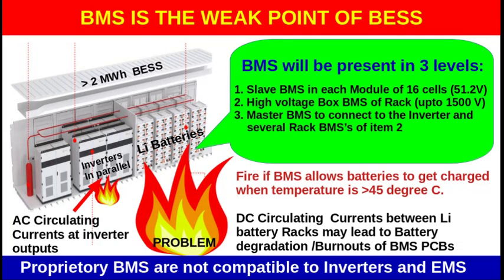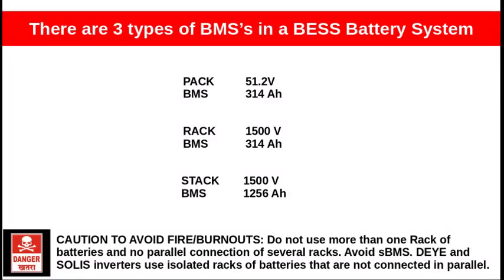The battery management system, BMS, is the weak point of a BESS. The BMS will be present in general in 3 levels inside the BESS. Fire will result if the BMS allows batteries to get charged when the temperature is above 45 degrees centigrade. There are 3 types of BMSs in a BESS. First is a pack BMS. The pack or battery has a voltage of 51.2 volt.